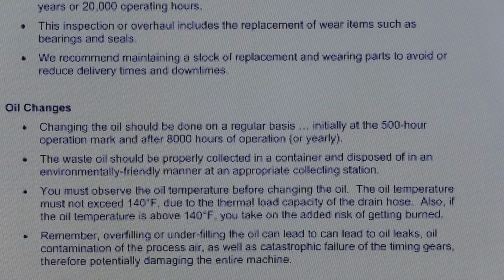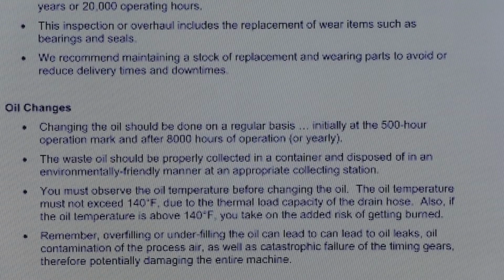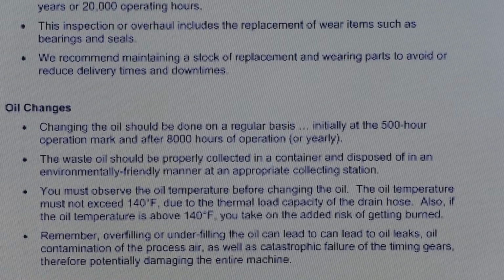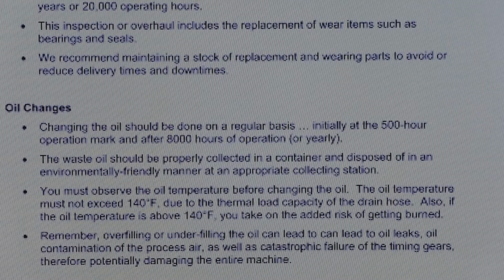The oil change is done with the oil that's in it. It's a 16,000 hour or 2-year oil. Now, just this week, my boss had a phone call from a customer that had an issue with a blower, who said, well, you said the oil was a 16,000 hour oil. They never bothered to look inside the cabinet and they had a leak. The blower's locked up now. So that's why we stress you need to at least look at the machines.